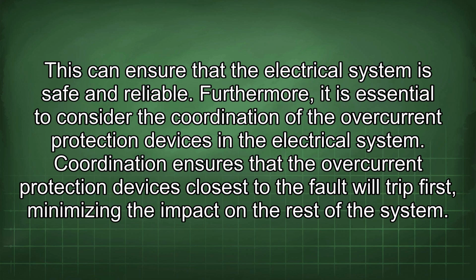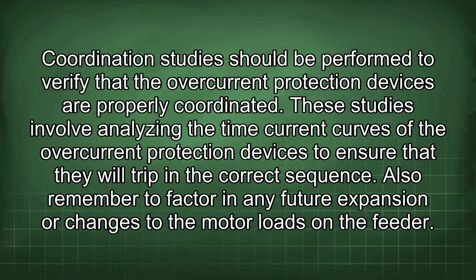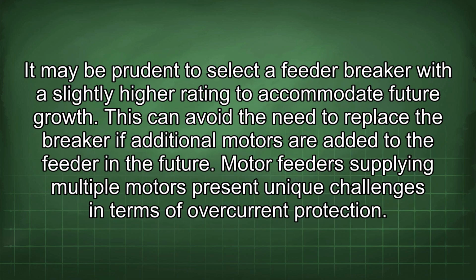Furthermore, it is essential to consider the coordination of the overcurrent protection devices in the electrical system. Coordination ensures that the overcurrent protection device closest to the fault will trip first, minimizing the impact on the rest of the system. Coordination studies should be performed to verify that the overcurrent protection devices are properly coordinated. These studies involve analyzing the time current curves of the overcurrent protection devices to ensure that they will trip in the correct sequence. Also remember to factor in any future expansion or changes to the motor loads on the feeder. It may be prudent to select a feeder breaker with a slightly higher rating to accommodate future growth.